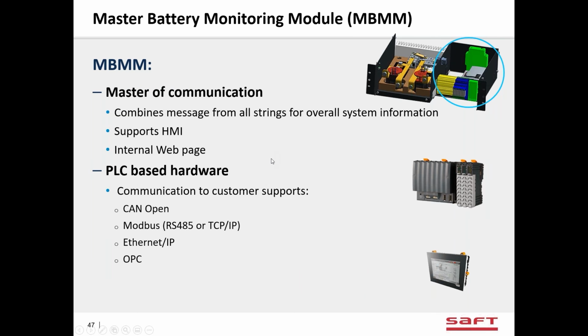The next piece of our battery management system is called the master battery monitor module, MBMM. This is an industrial PLC that talks to all the battery's strings through the BMM. So it monitors all of the strings and displays the information on the screen as if that's all one big battery. So you can look at the highest temperature in the whole set. You can look at the lowest and highest voltage in the whole set, currents for the whole battery group. And then you can also, with menus, drill down into information about each string, and even display individual cell voltages in the whole battery on the display.